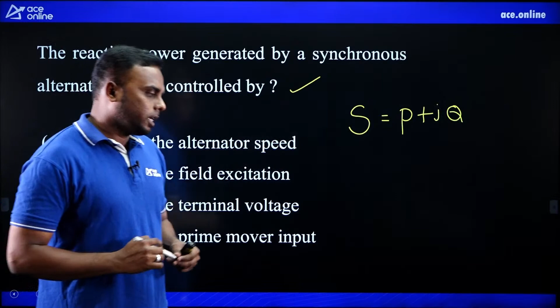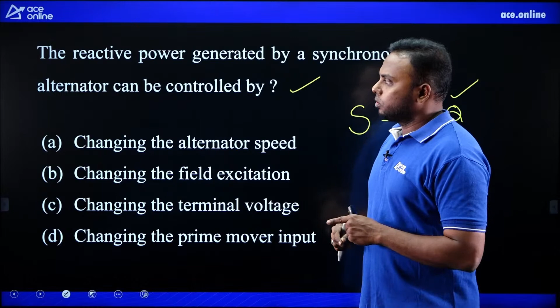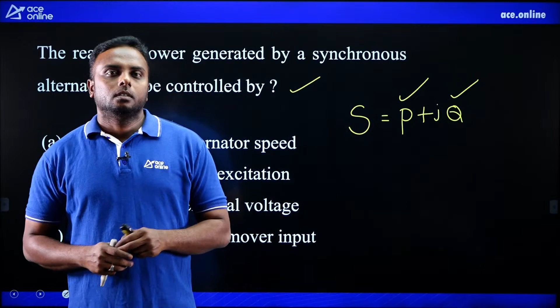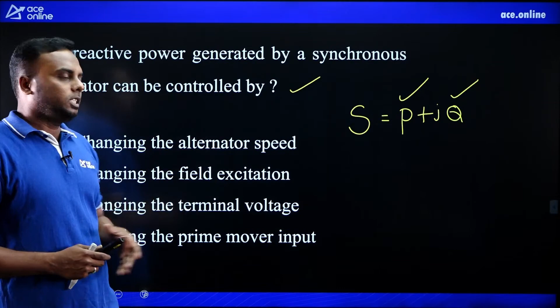So there is active power and reactive power both in generators or alternators. If you want to control particularly the reactive power of an alternator, which one do we have to change? Similarly, to change the active power, which one do we have to change mainly? In an alternator we mainly have two variations: one is excitation variation, and the other is mechanical input variation, or turbine input.